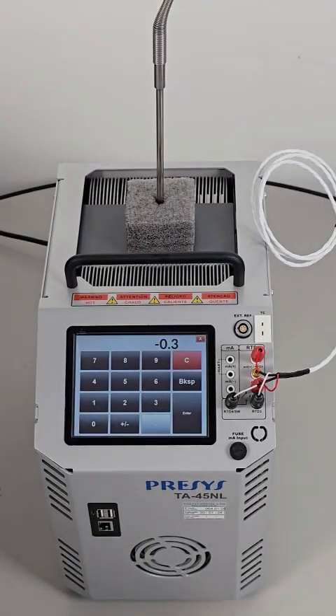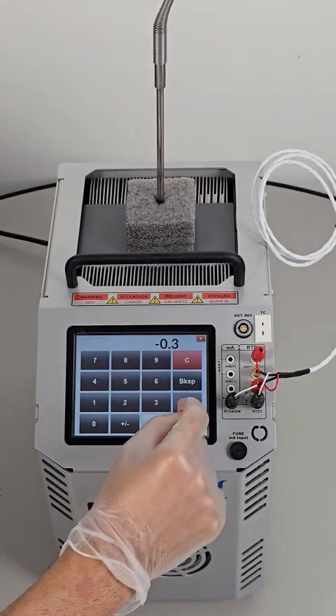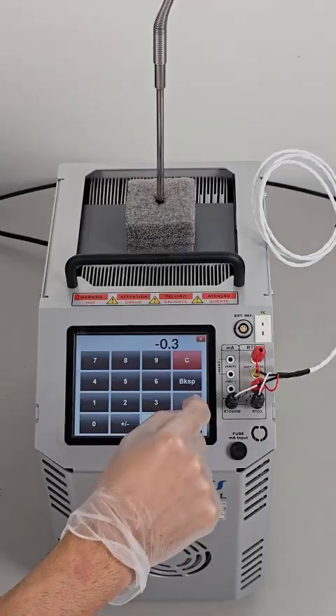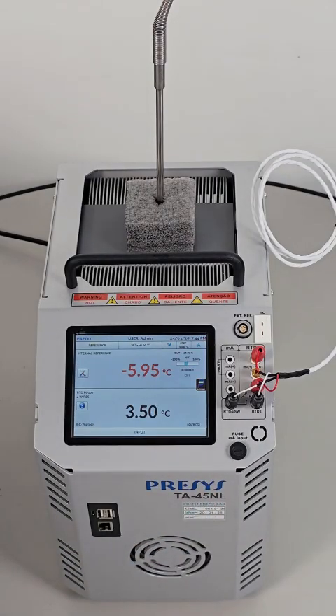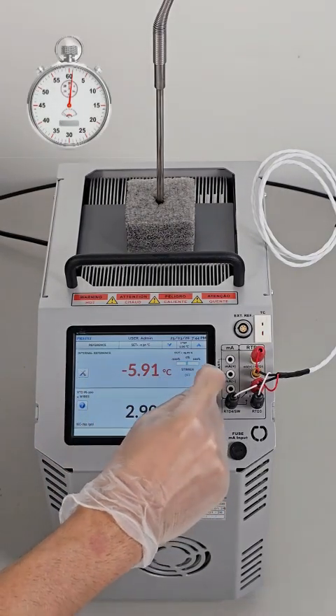Adjust the set point to minus 0.3 degrees Celsius to preserve the ice mantle for extended periods, preventing both excessive growth and melting of the ice layer. Reinstall the monitoring sensor in the re-entrant well to follow stabilization.